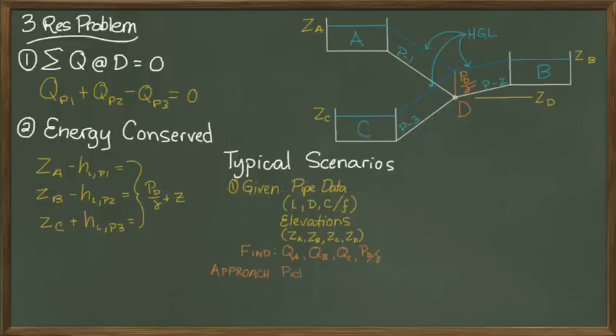The approach to this particular problem is to pick a value for the pressure head at point D such that the summation of the flow into or out of point D is zero. In other words, once you have a guess for the pressure at D, then you can solve for the head losses getting to or from D for each of the water sources.